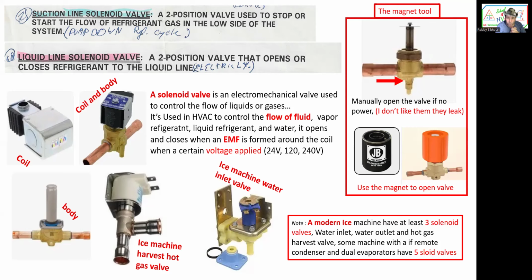Anyway, note, a modern ice machine has at least 3 solenoid valves: inlet water, outlet water, and hot gas valve for defrost, for harvest. Some machines with a remote condenser could have up to 5 solenoid valves: liquid line valve, hot gas valve, water inlet, water outlet, and another liquid line valve if it's a dual evaporator.